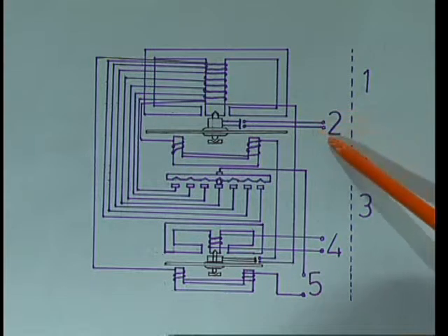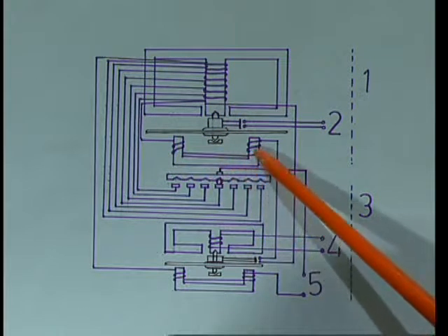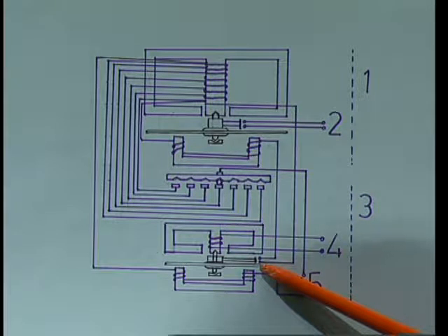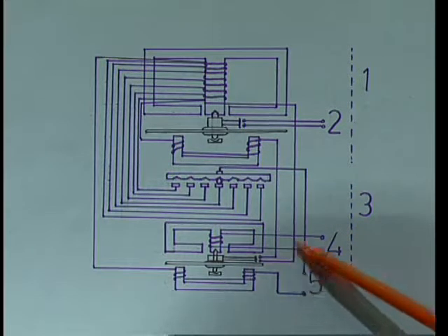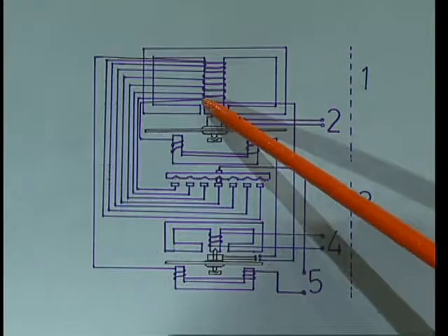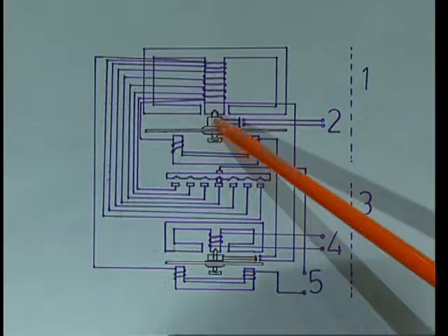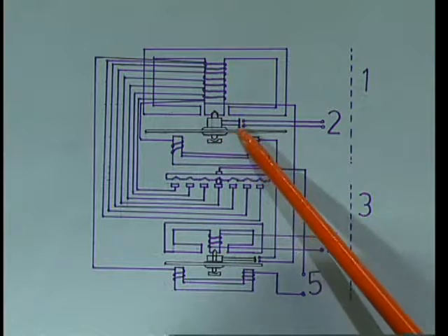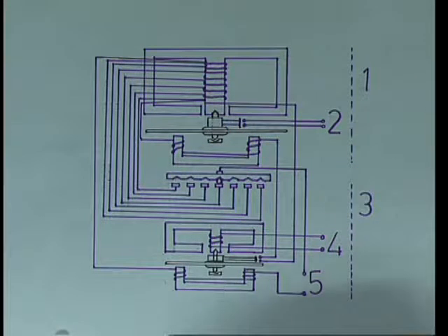Here it is the trip circuit contacts. The lower electromagnet also has a winding, and this winding is connected to the fixed contacts of the directional power relay. So this is one winding, one terminal, and this is another terminal connected here on the central limb, which carries an aluminum disc. This disc is provided with a spindle, and the spindle carries a moving contact. So this is the construction of a directional overcurrent relay.